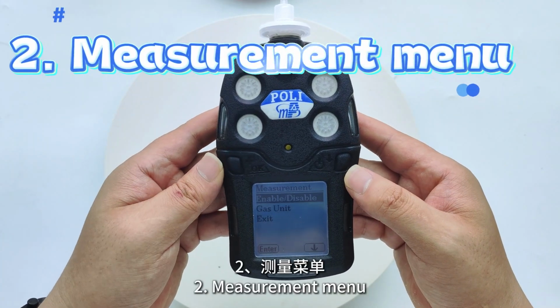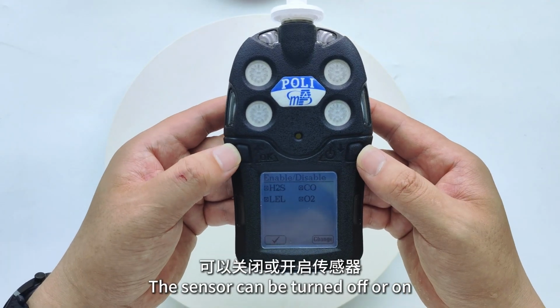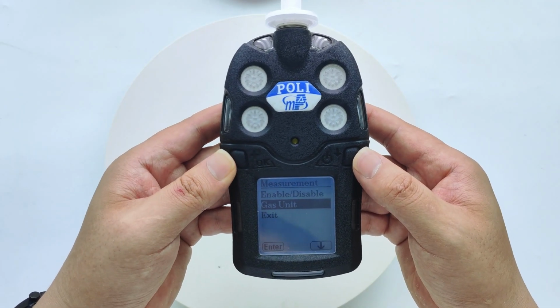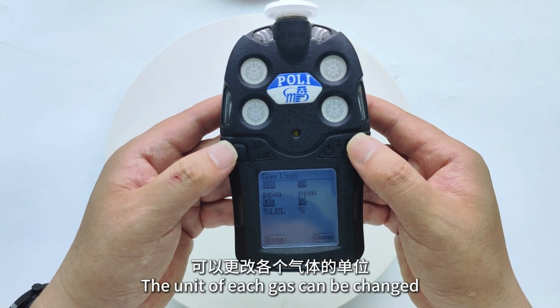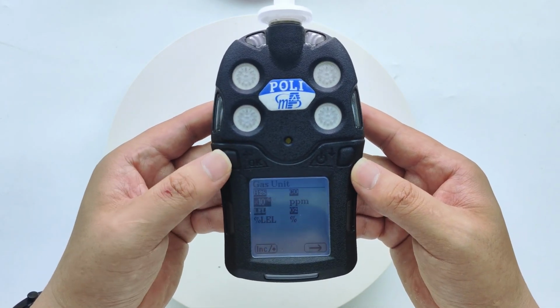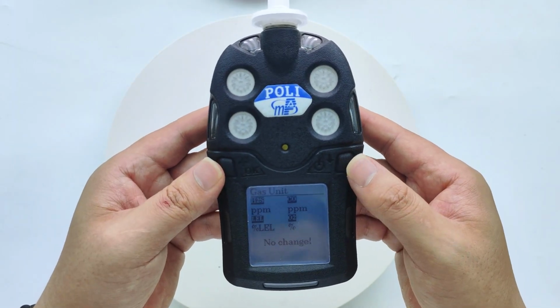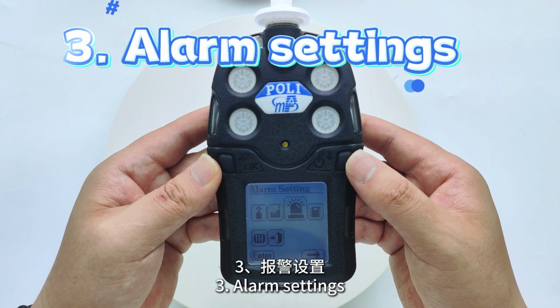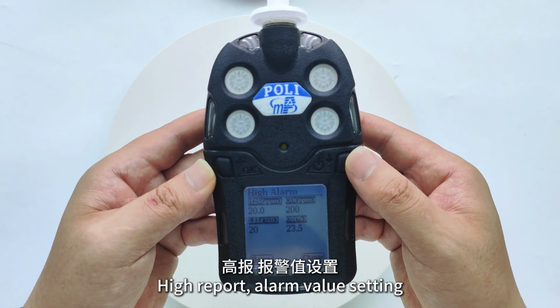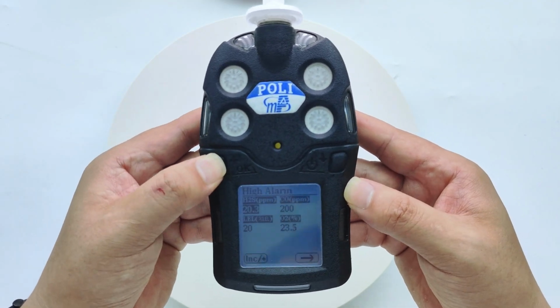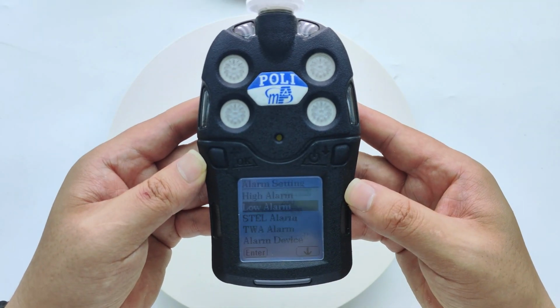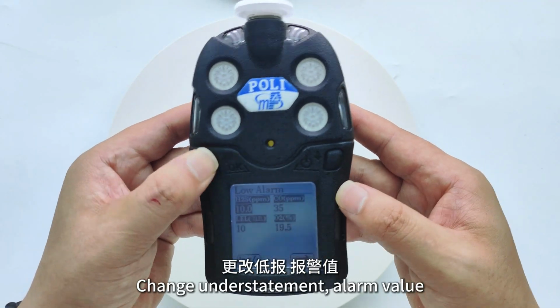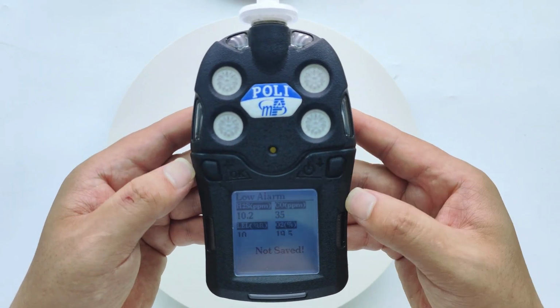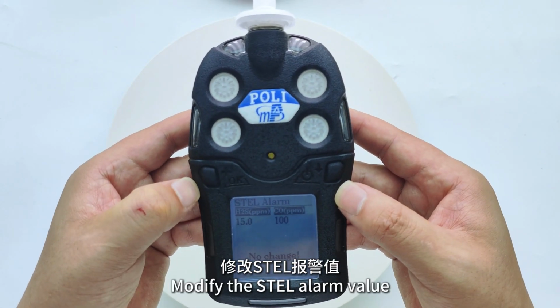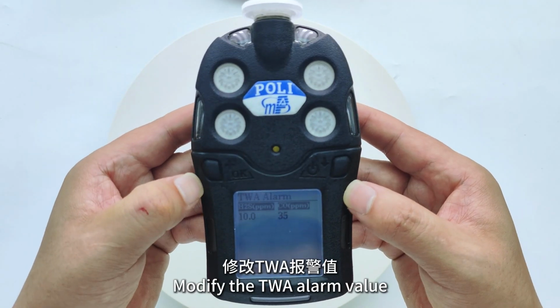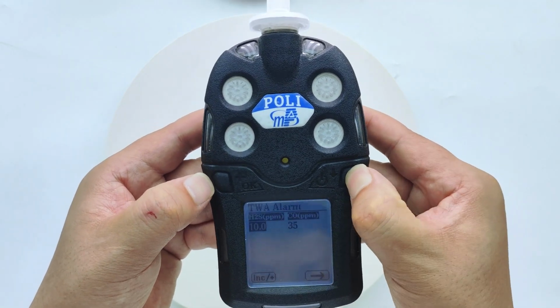2. Measurement menu. The sensor can be turned off or on. Gas unit. The unit of each gas can be changed. 3. Alarm settings. High alarm value setting. Change the low alarm value. Modify the STEL alarm value. Modify the TWA alarm value.